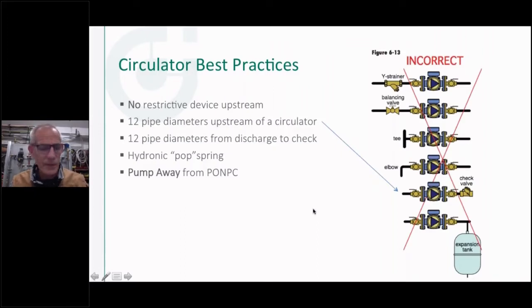I like them a little bit better than flow checks. You know, the old weighted style flow check, it just seems like a lot of iron, a lot of technology to do a simple thing, which is a half a pound of weight that the circulator opens up or pops open when it starts.